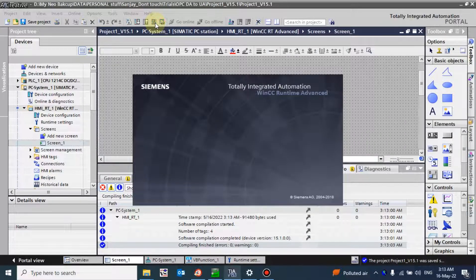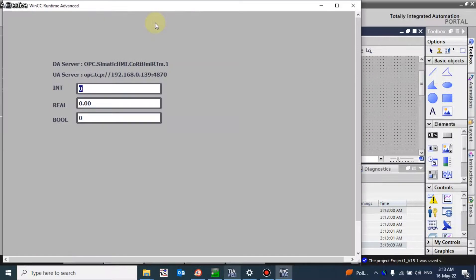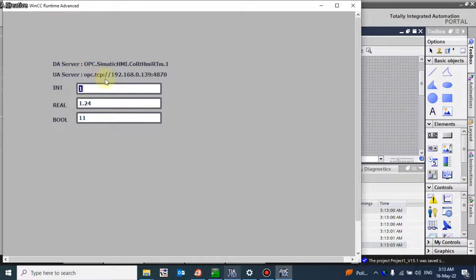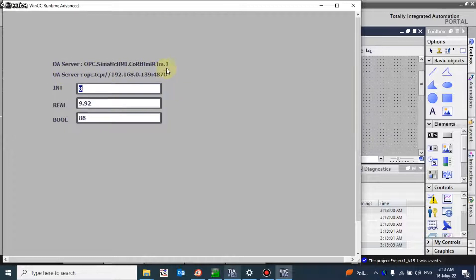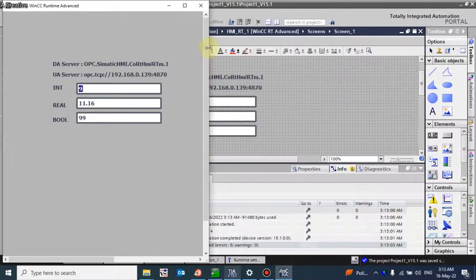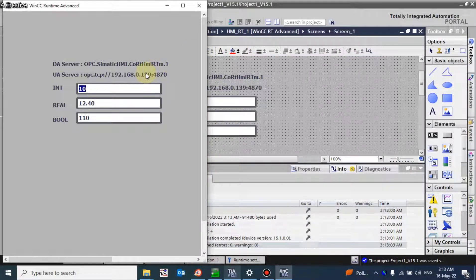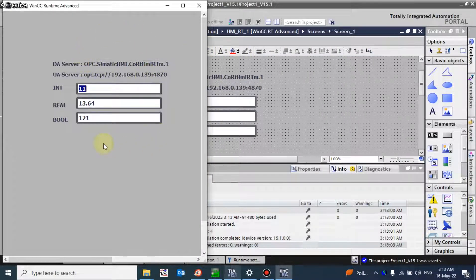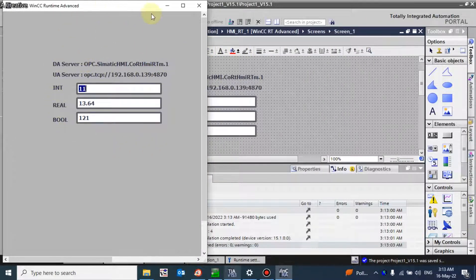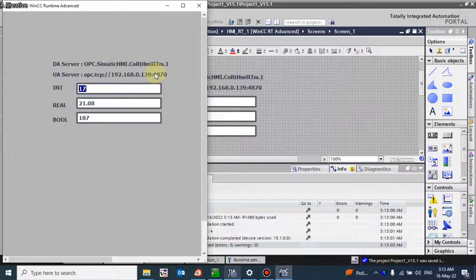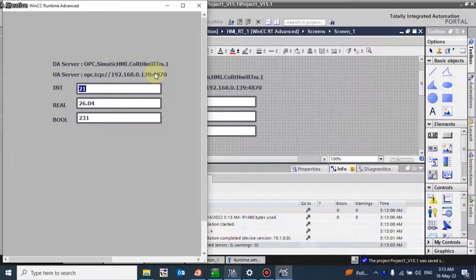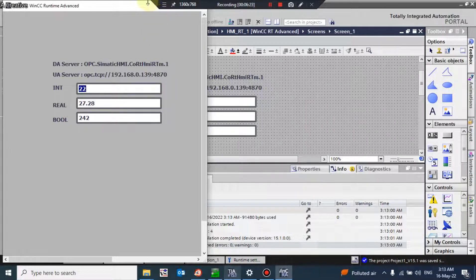Start simulation. Now I have mentioned here my IP address - the IP address of the system is 192.168.0.139 and this is my port. My SCADA is transferring all the tags to this OPC server address, so the client has to connect with this address and the client will get all the data from my SCADA to the client side. We have only a single machine or computer here running server and client on the single platform, but you can create networking and you can get all the data to your network clients.